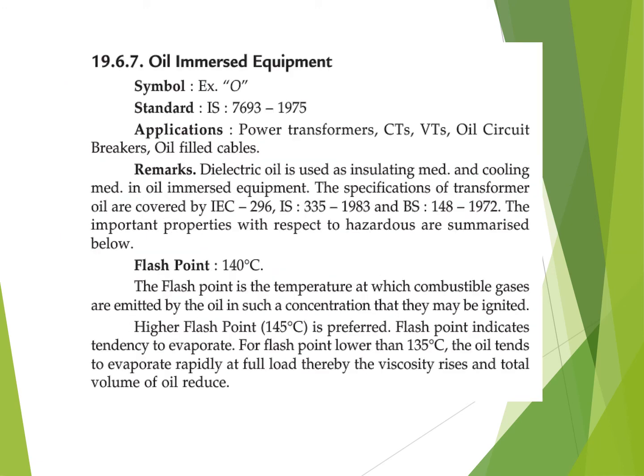Oil immersed equipment is mainly equipment immersed in oil. So if the equipment produces any spark, the oil acts as an insulating medium, or the oil suppresses the spark. Especially in a transformer, we know the winding and core, everything is immersed in oil. So it has two purposes. One is cooling, and the other is that any spark can be avoided. So this dielectric oil is used as the medium. Here the flash point is 140 degrees Celsius, so it may prevent this.